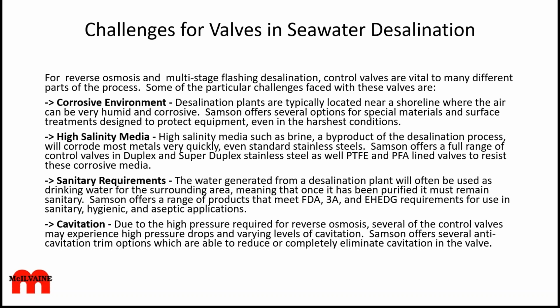The water generated from a desalination plant will often be used as drinking water, meaning it has to be purified and remain sanitary. So you need to design valves to meet FDA and other sanitary, hygienic, and aseptic application requirements. Cavitation with these big pumps is certainly another problem. Due to the high pressure required for reverse osmosis, several control valves may experience high pressure drops and varying levels of cavitation. Samson offers anti-cavitation trim options which are able to reduce or completely eliminate cavitation in the valve.